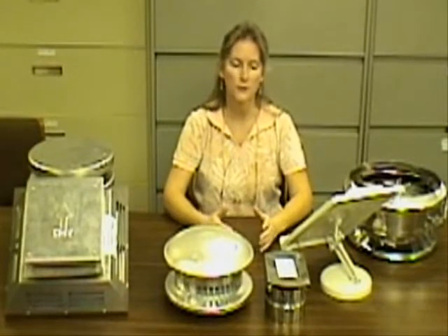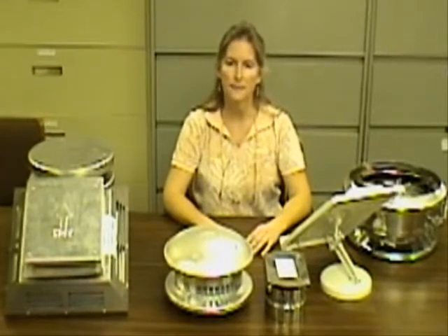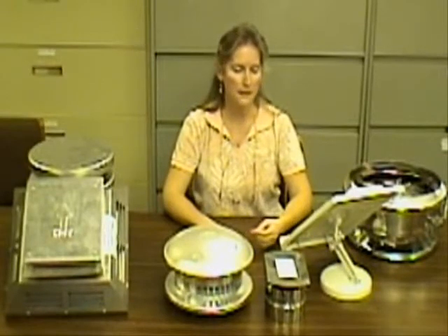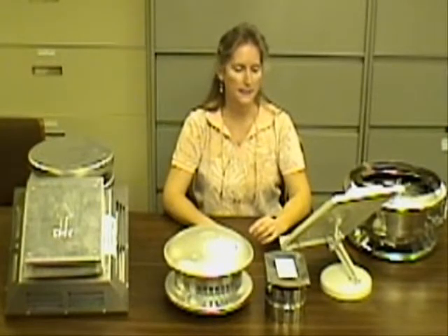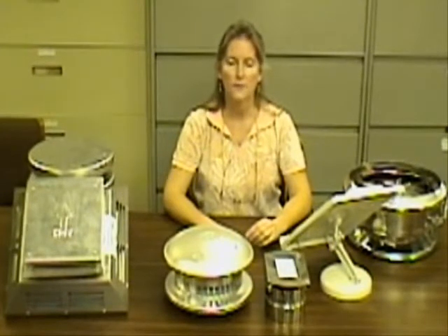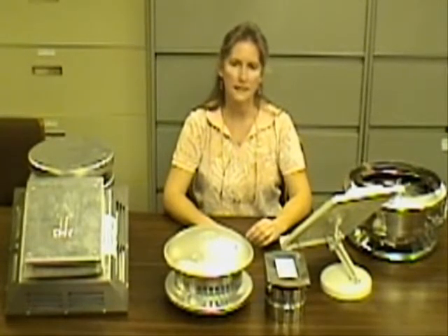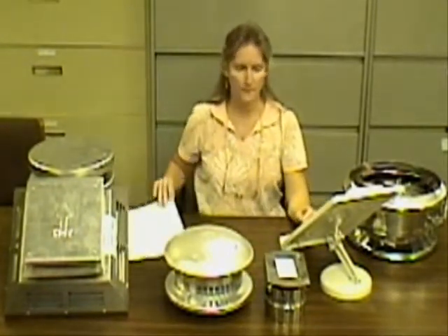Some of our venting products are used with appliances that have some mechanical push to them that helps get rid of the flue gases. These appliances have a slight positive pressure in the vent, thus they can terminate horizontally because they aren't relying solely on natural draft. The vents for these appliances then have the option of venting horizontally or vertically, whichever the homeowner chooses. The vents for these types of appliances are also designed with sealed joints or gaskets at the joints that then prevent the flue gases from exiting through the vent itself.